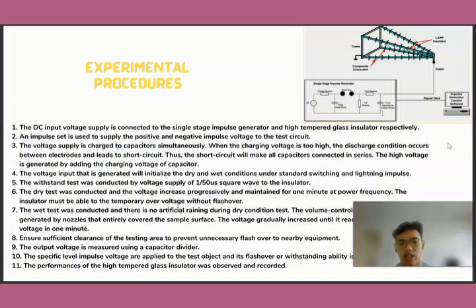Sixth, the dry test will be conducted and the voltage increases progressively and is maintained for 1 minute at power frequency. The insulator must be able to withstand the temporary overvoltage without flashover. Seventh, the wet test is conducted, and there is no artificial rain during the dry condition test. The volume-controlled artificial rain is generated by a motor that will entirely cover the sample surface, so that the voltage will gradually increase until it reaches the temporary overvoltage in 1 minute.